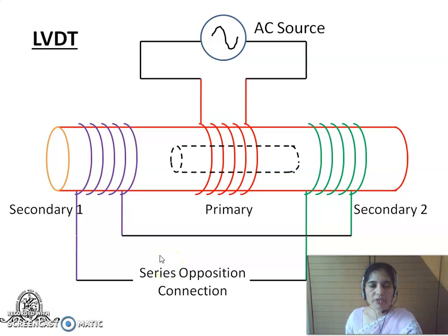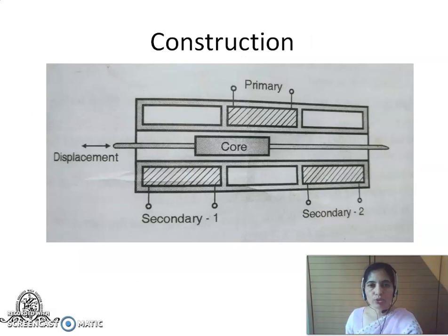There is a movable core in the cylindrical pipe, and a rod is brought out from this core. With this rod, one can move the magnetic core inside the cylinder. Therefore, this is a movable core which will be used to capture the displacement which is to be measured. This shows a two-dimensional figure of the LVDT, and it shows the three main components: the primary in the top section, the two secondaries in the bottom section, and the movable core in between the primary and the secondary. If the core is exactly at the center, just below the primary, then this position of the core is the center position, also called the null position.